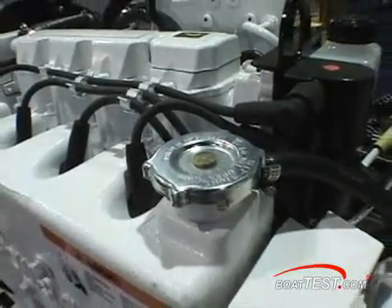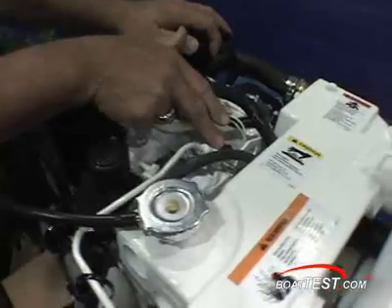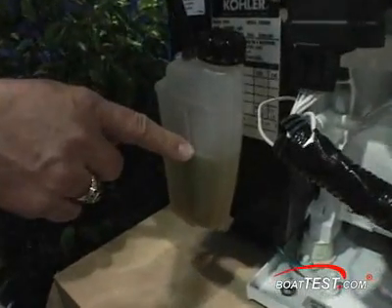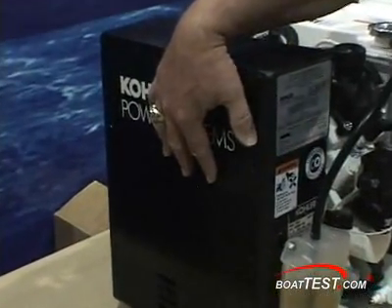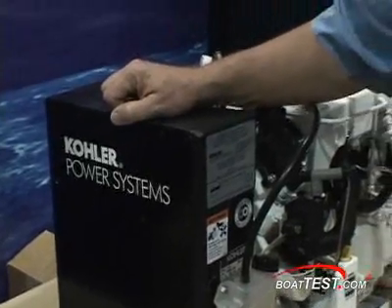This compact unit fits in the same space as older generator models. It features a fuel injection system, spin-on oil filter with drain or barbed fitting for an oil changer system, fresh water cooling system with overflow tank, and a seawater pump for raw water cooling. These units have no air filter to clean or change and no belts to break. You do have basic service for oil, fuel, and water systems, and enjoy reliable power delivery.